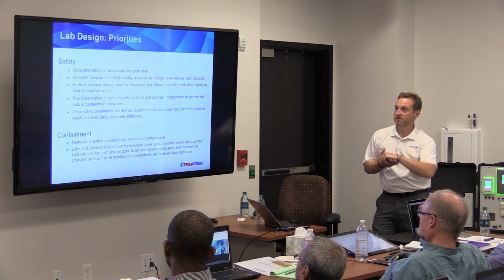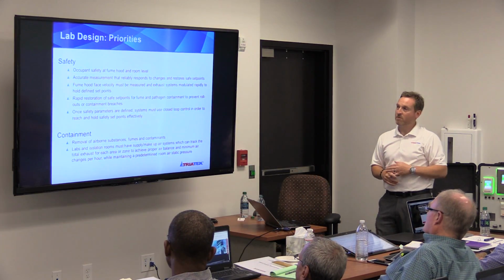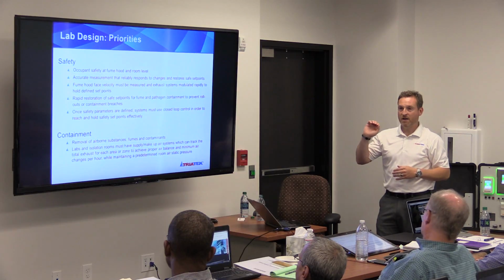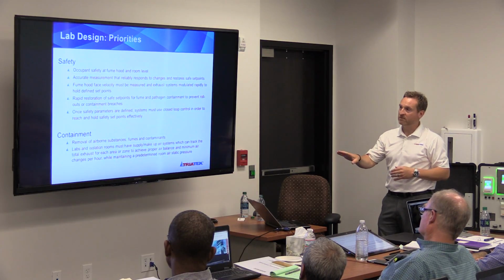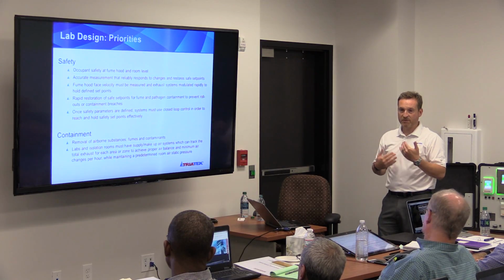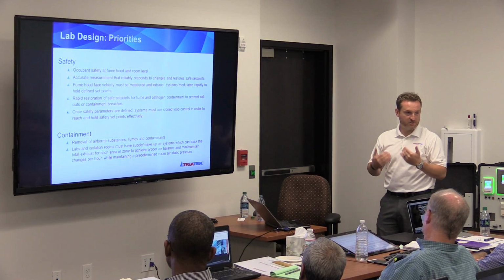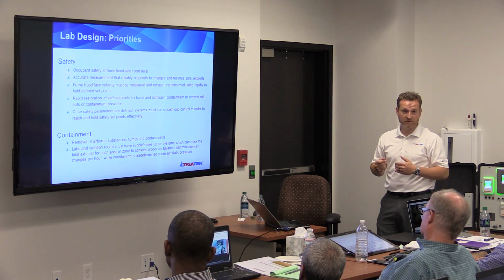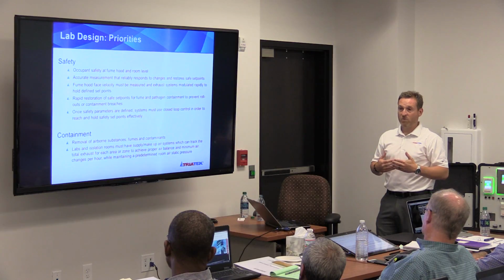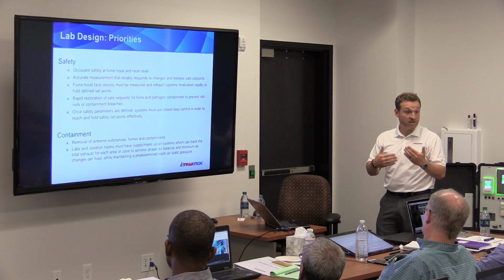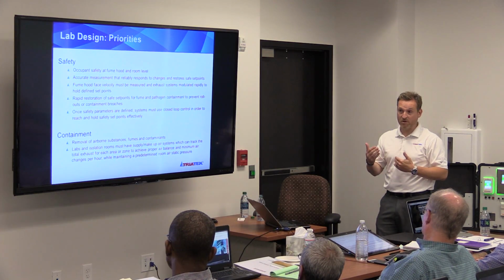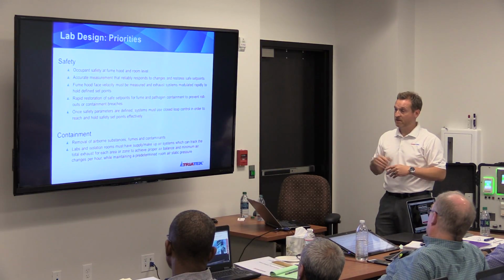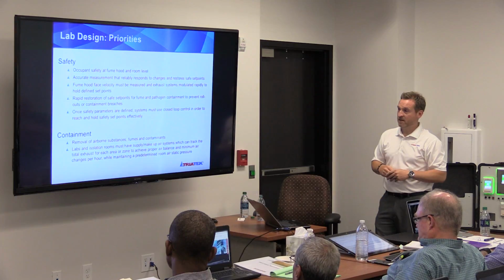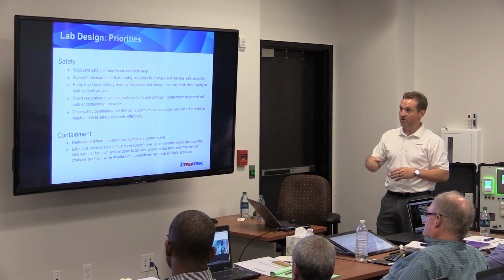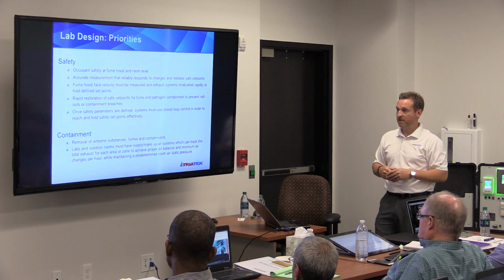Typical design priorities are going to be safety being first and foremost, both at the room level and the fume hood level. These systems have to accurately measure and reliably respond to changes, and they have to do it within seconds. Okay, and we also have to do this without any variation or oscillation or hunting. So it's high-speed control, but it's very precise control. All right, and we'll get into some of how we do that here momentarily.